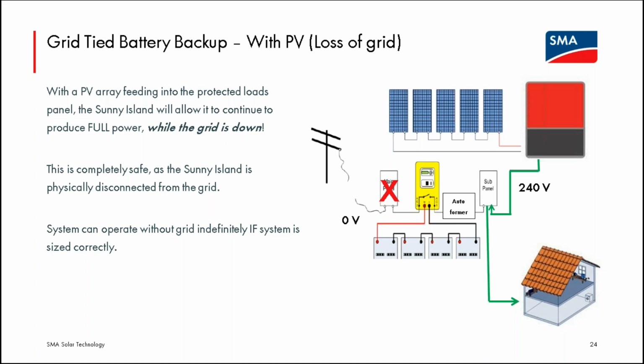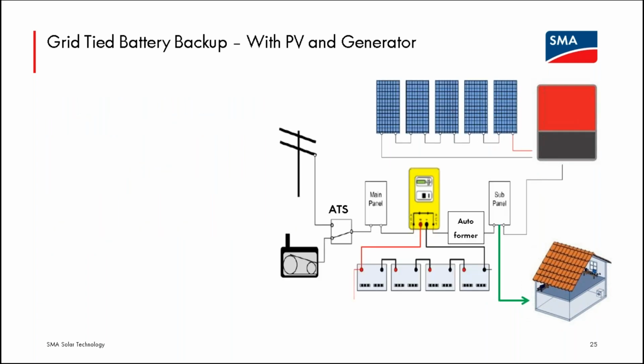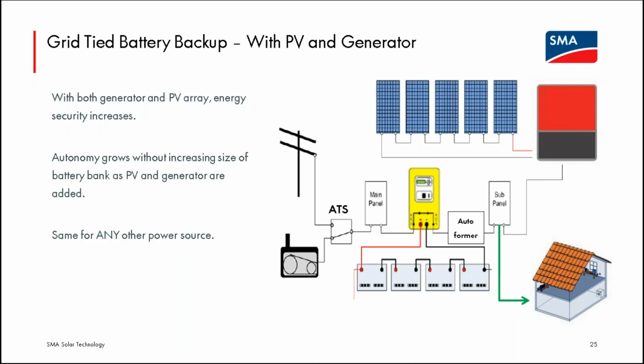Obviously, there will be situations where the PV system won't be able to provide that much power. Maybe whatever caused the utility grid to fail damaged the PV array, or there's just several days of very bad weather. Most systems will want as many potential sources of power to be available should the grid fail. So often, very often, you would have a generator as well. And we're showing to the left the grid and the generator come into something labeled ATS, automatic transfer switch. That transfer switch can be automatic, it can be manual, but some way of switching between utility power and generator power, and the output of that switch needs to come to the AC2 terminals of the Sunny Island.